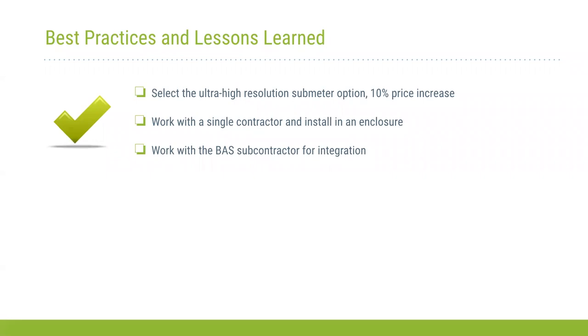Work with a single contractor to install the enclosure. Make sure you have a source of energy in the enclosure to power the device, ensure all the cabling is run, and include any integration programming that needs to be done. Best practice for us: a lot of our O&Ms have ongoing BAS subcontractors, so our O&Ms could work with their BAS subcontractor to do the integration during one of their normal monthly visits.